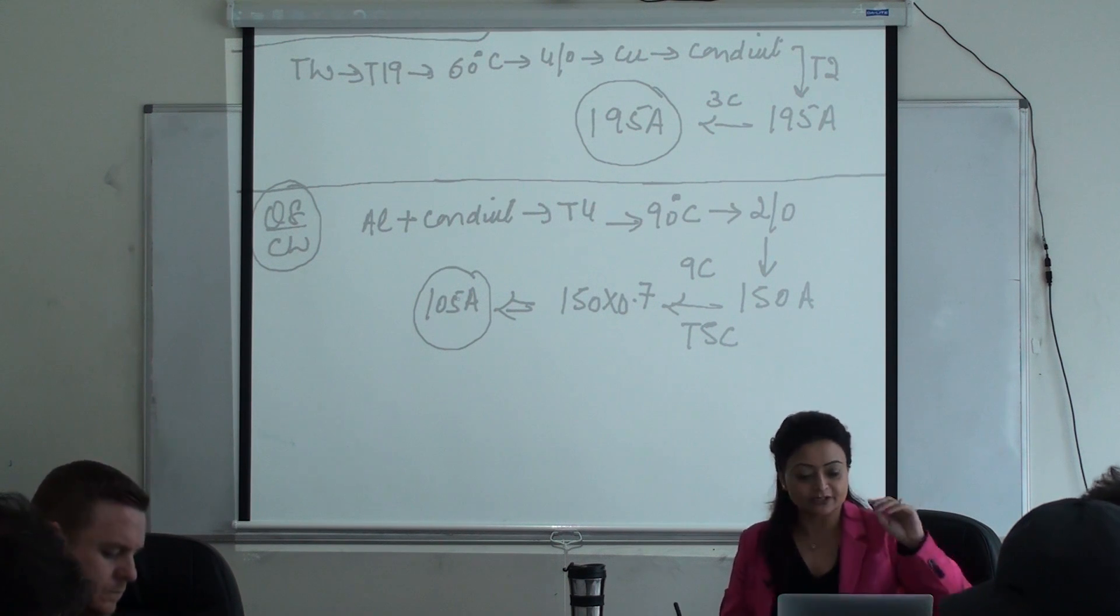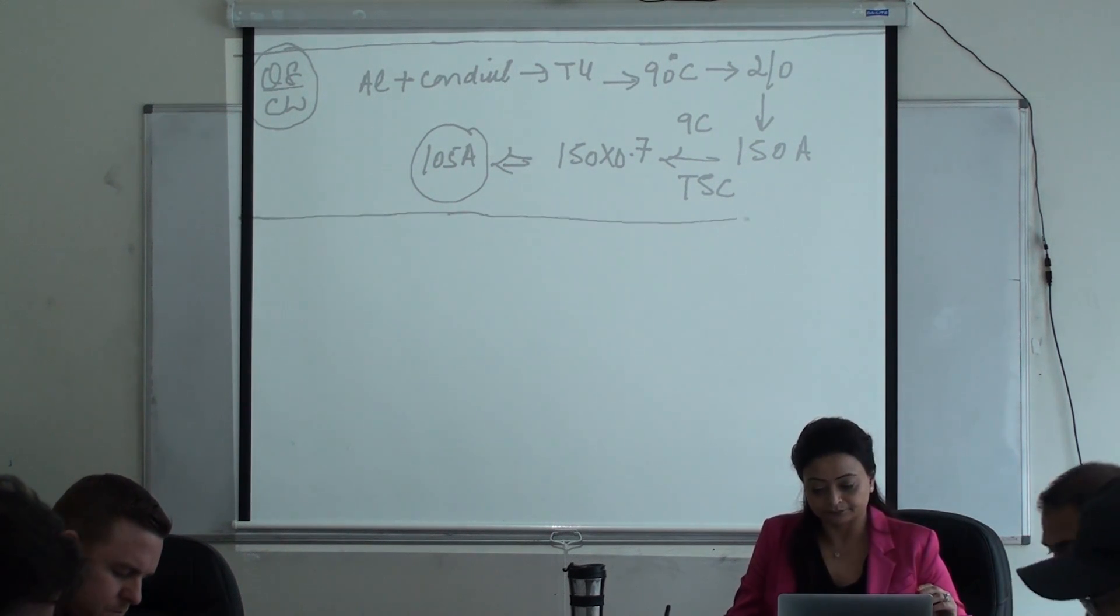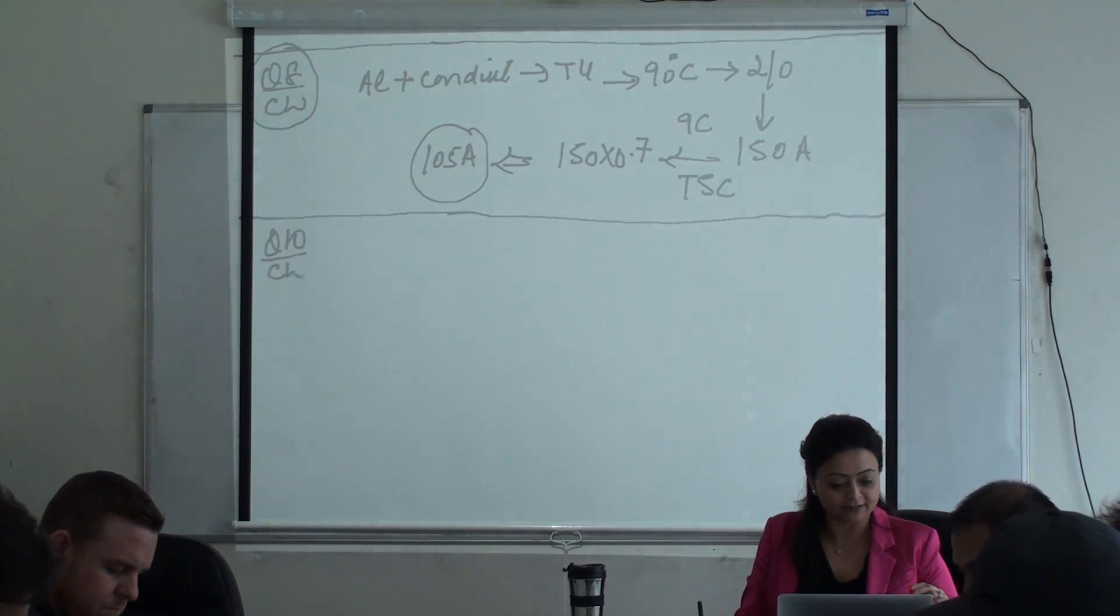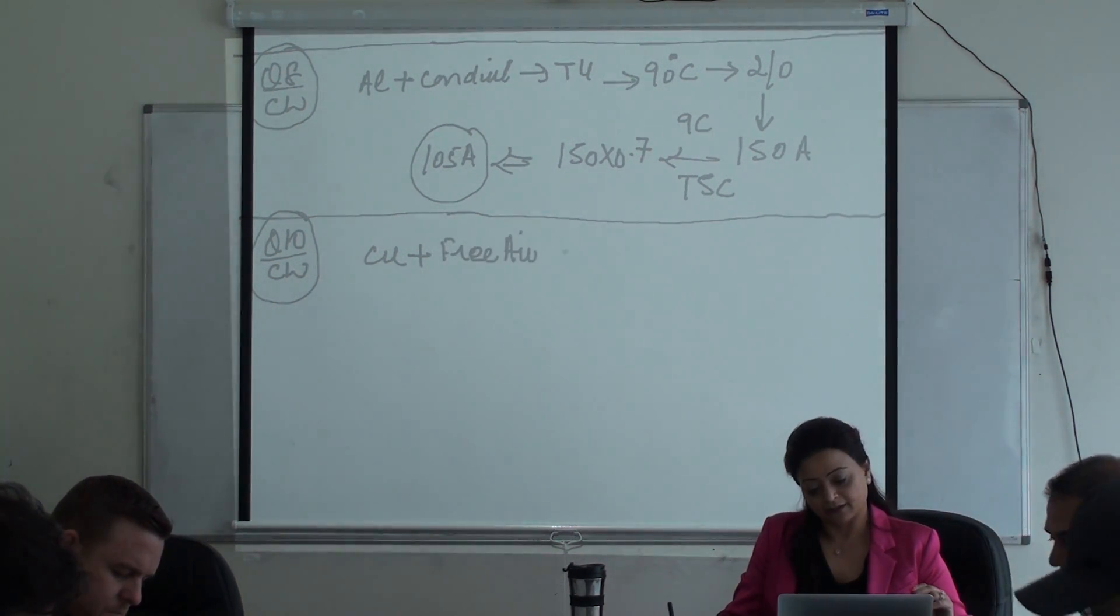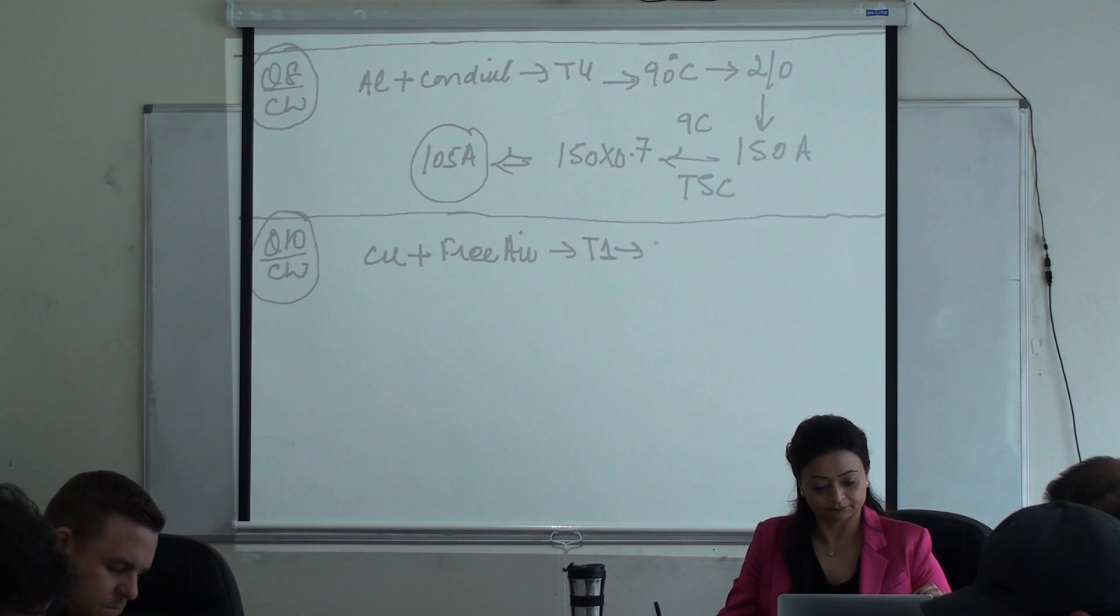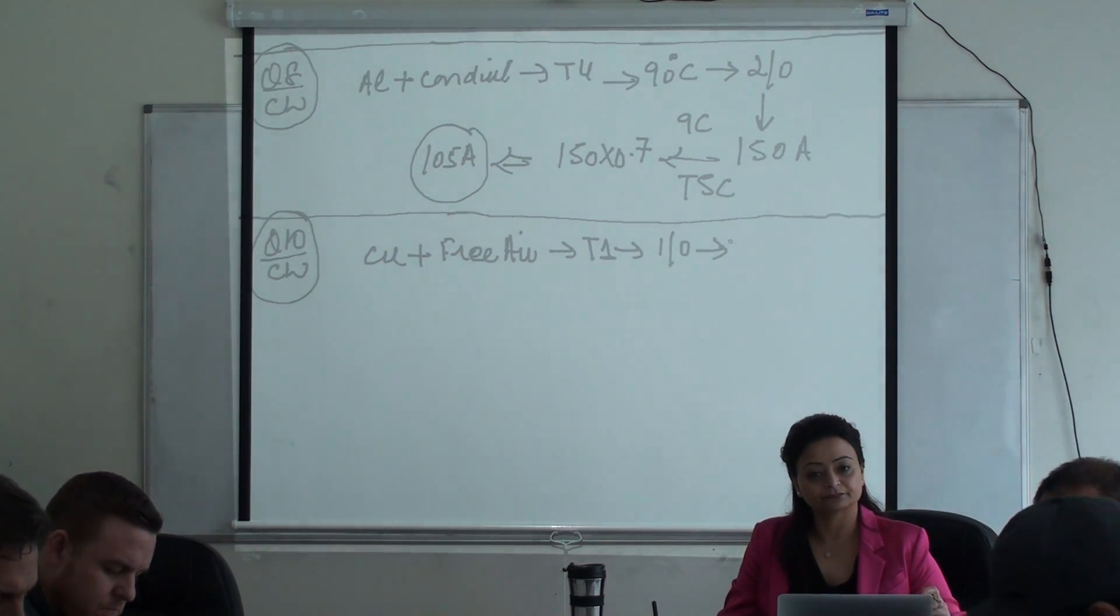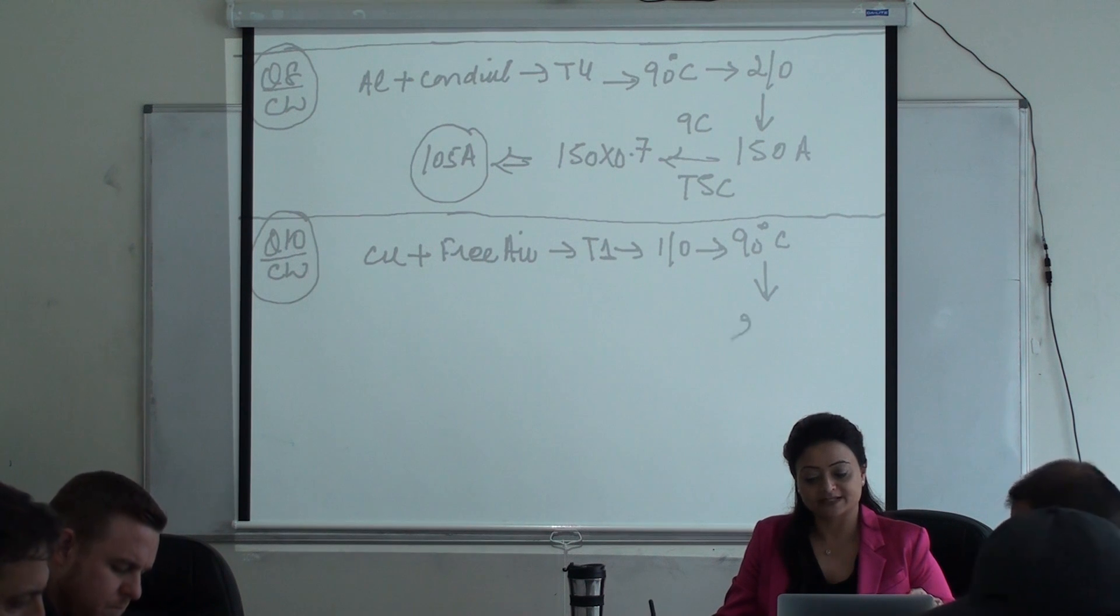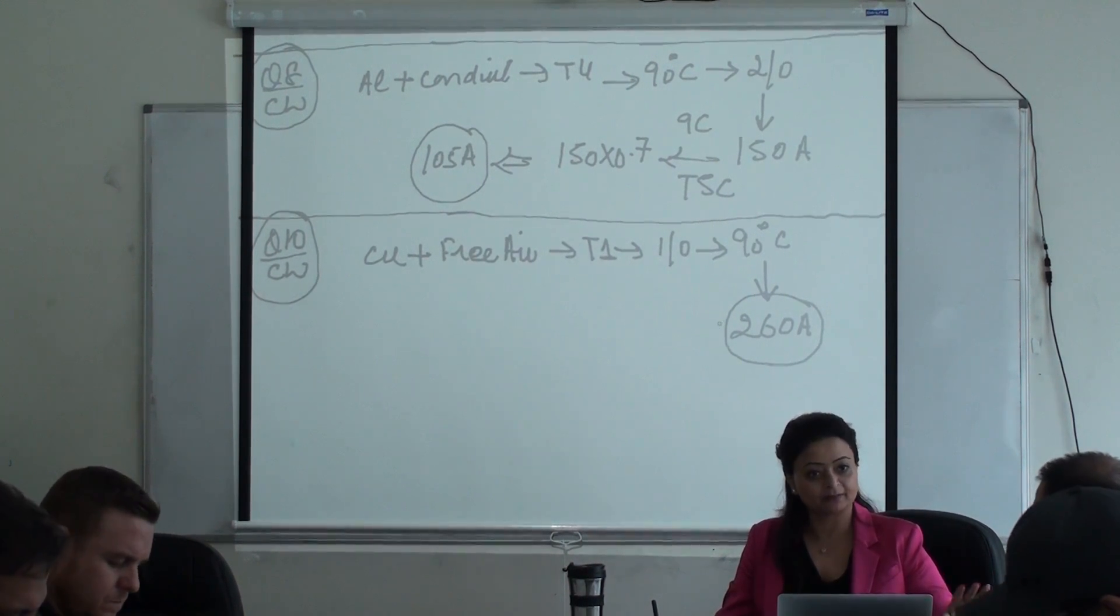Next question, number 10. Copper or aluminum? Copper. Free air or conduit? Free air. So we stick to our table one. What's the conductor size given here? One zero. And 90, 75, or 60 column? What is the degree C? 90 degree C. Perfect. Based on table one, how many amps? 260. That's it, no more information. Are we done?